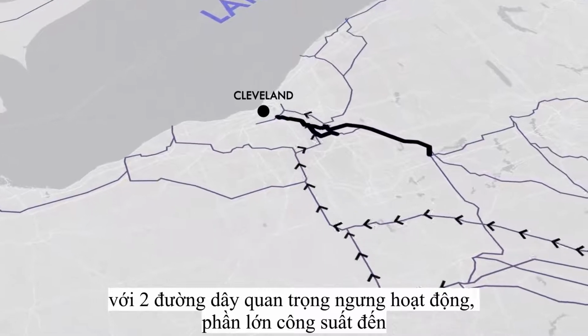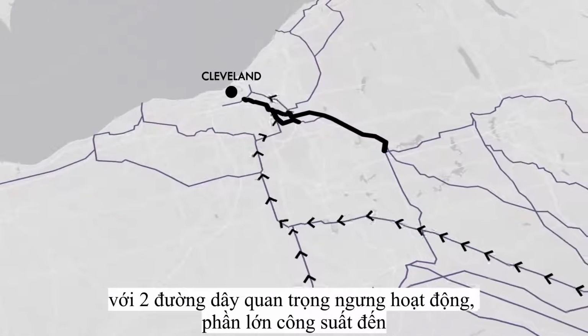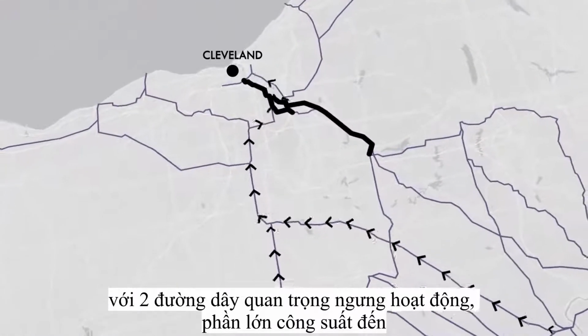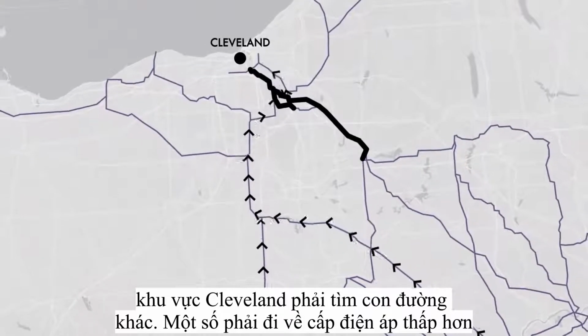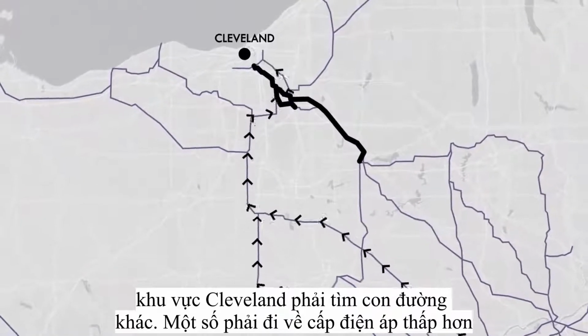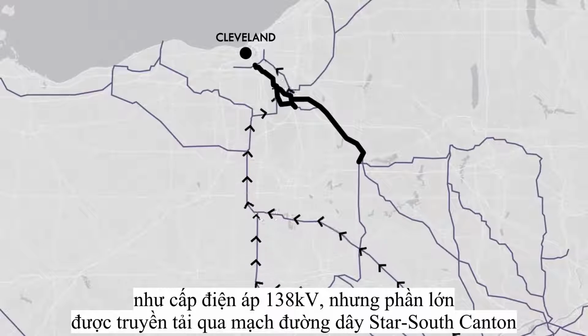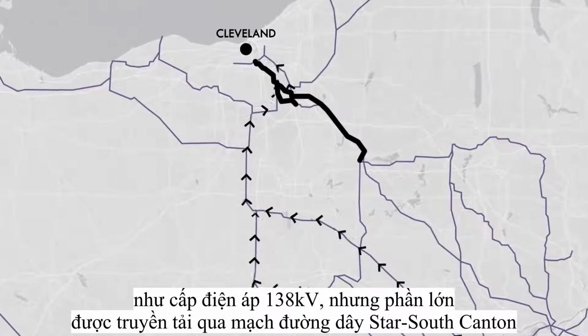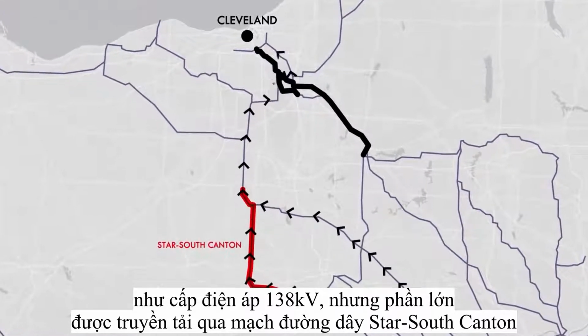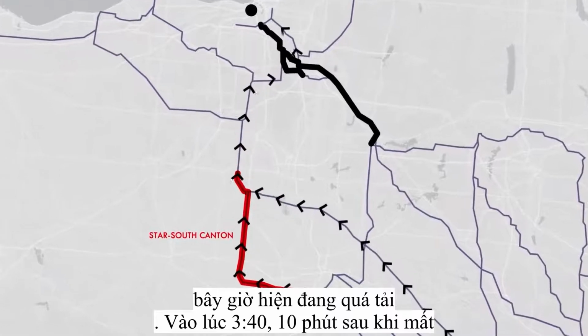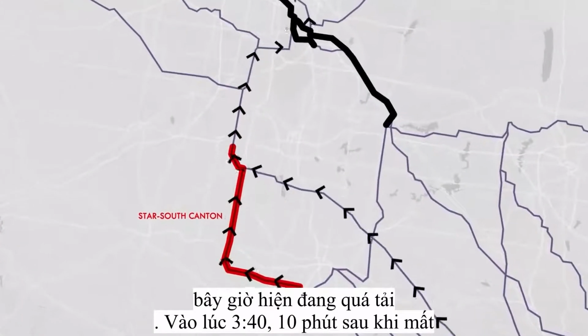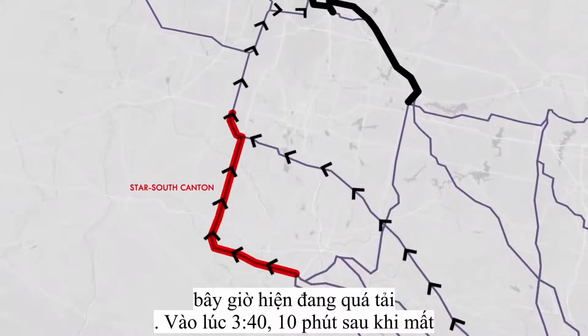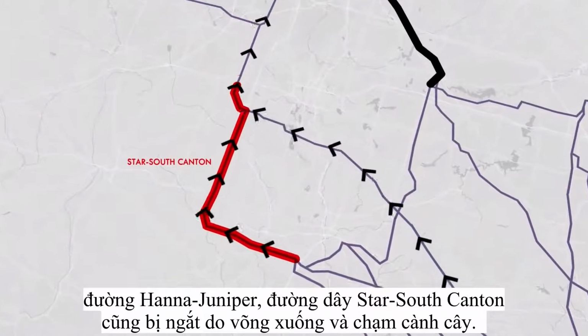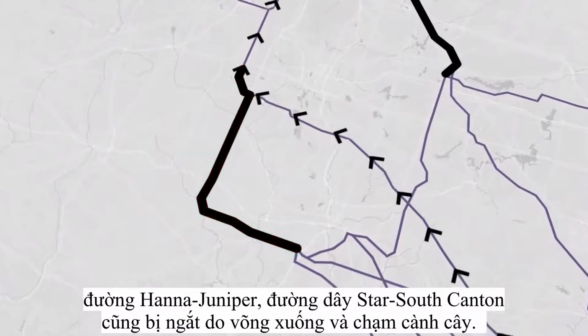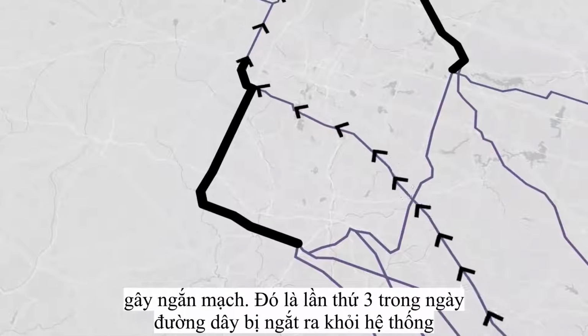With 2 key transmission lines out of service, a major portion of the electricity powering the Cleveland area had to find a new path into the city. Some of it was pushed onto the less efficient 138 kilovolt system, but much of it was being carried by the Star South Canton line, which was now carrying more than its rated capacity. At 3:40, a short 10 minutes after losing Hannah-Juniper, the Star South Canton line tripped offline when it too sagged into a tree and short-circuited.